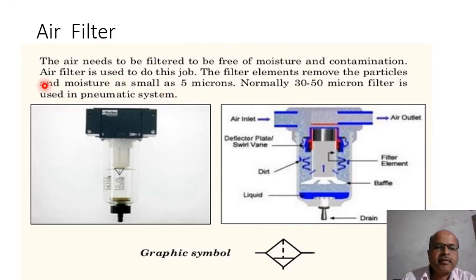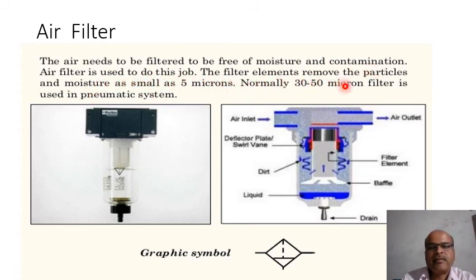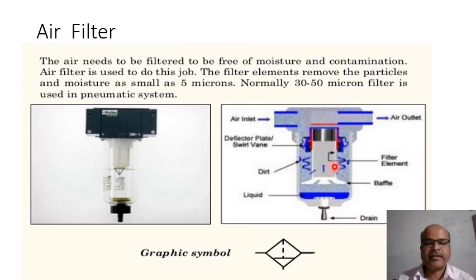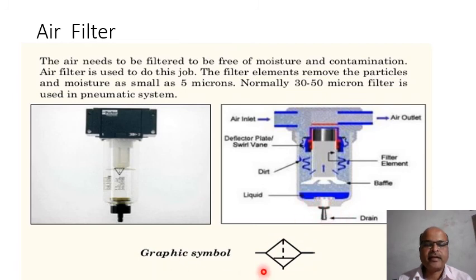Air needs to be filtered to be free from moisture and contamination. The filter element removes particles and moisture as small as 5 microns. Normally a 30 to 50 micron filter is used in a pneumatic system. This is the air filter structure as shown in the diagram — air inlet, air outlet, filter element, liquid collected at the downward side, drain, and the graphical symbol of the air filter.